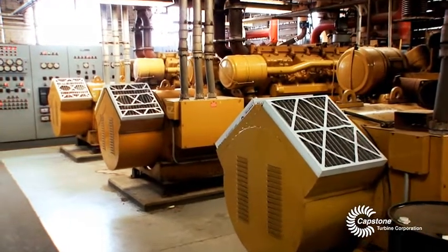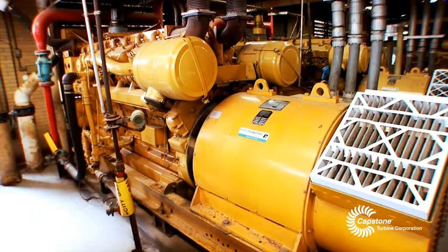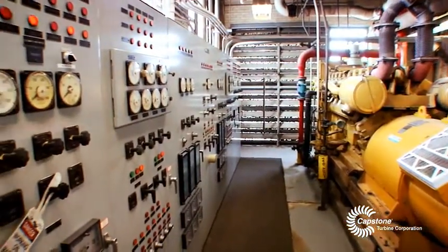We utilize our methane gas that we produce on site here with our internal combustion engines to produce about 20% of our power needs. The first 5 years there were very little maintenance costs, but as time has gone on and technology has changed and those engines have aged, they've pretty much become a money pit for us.